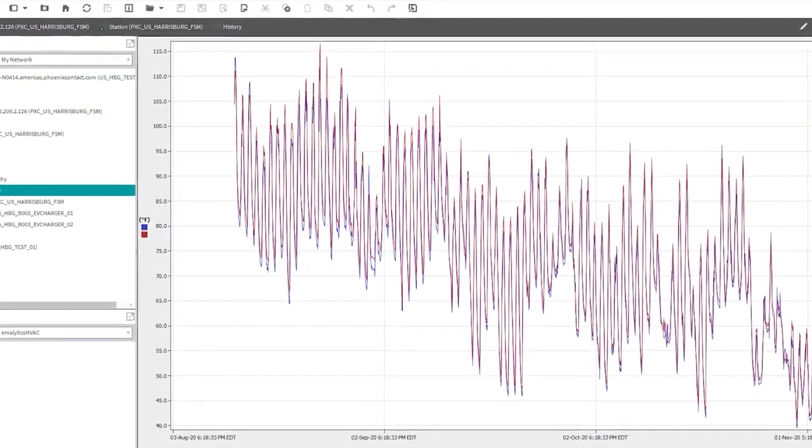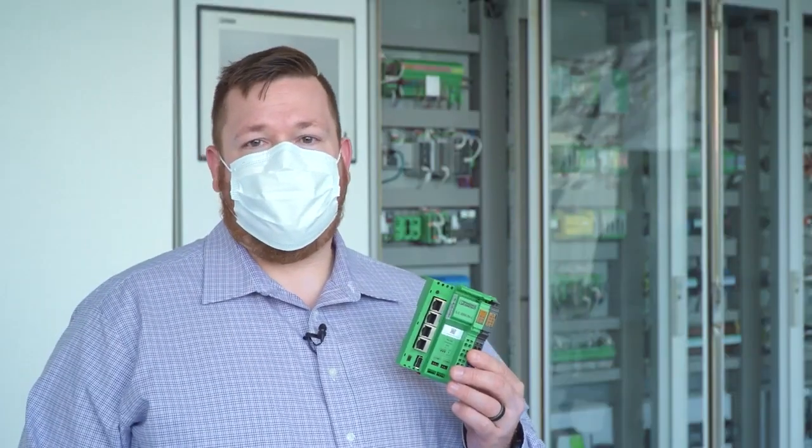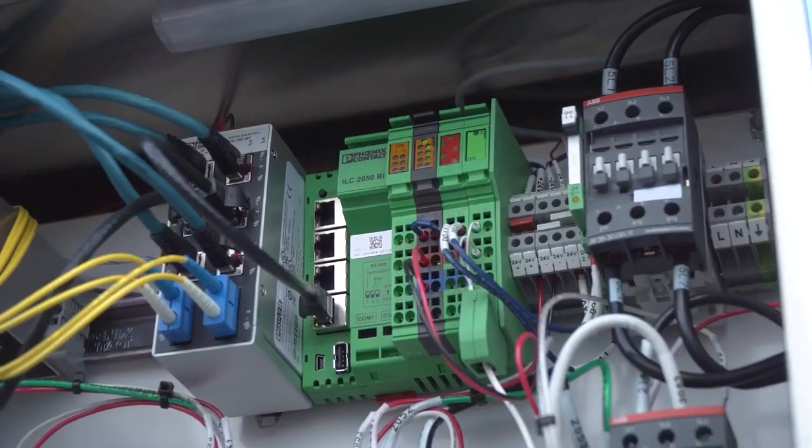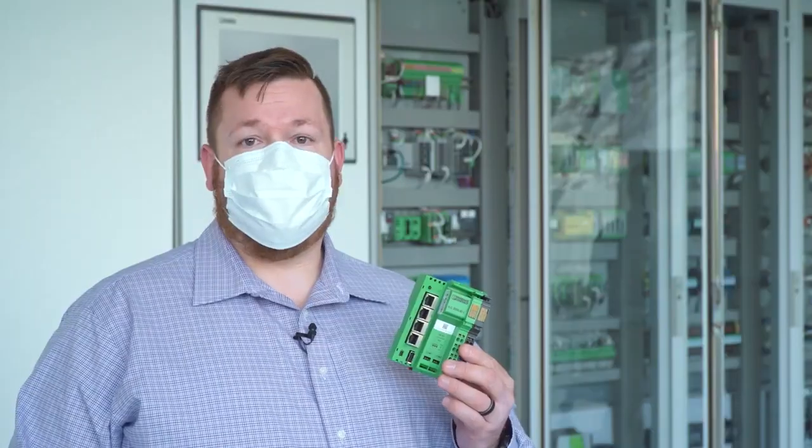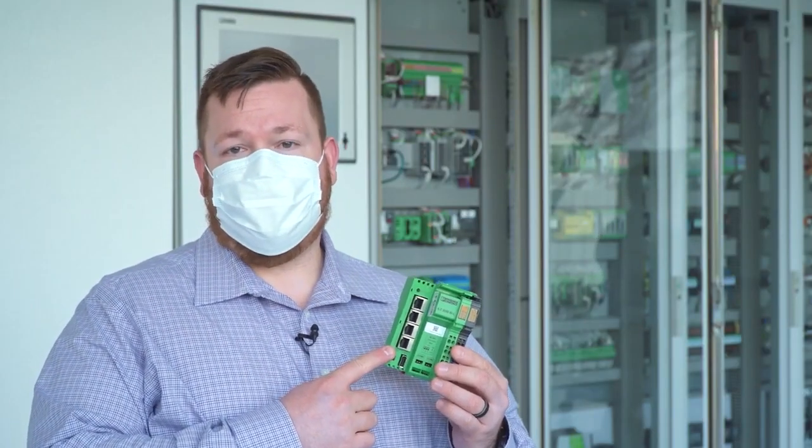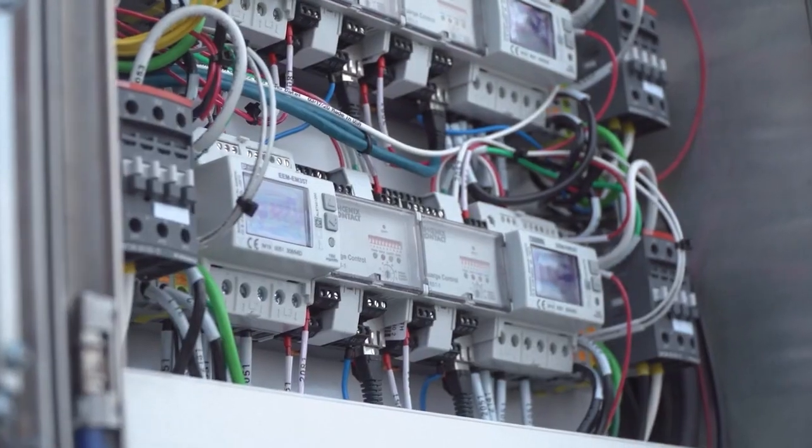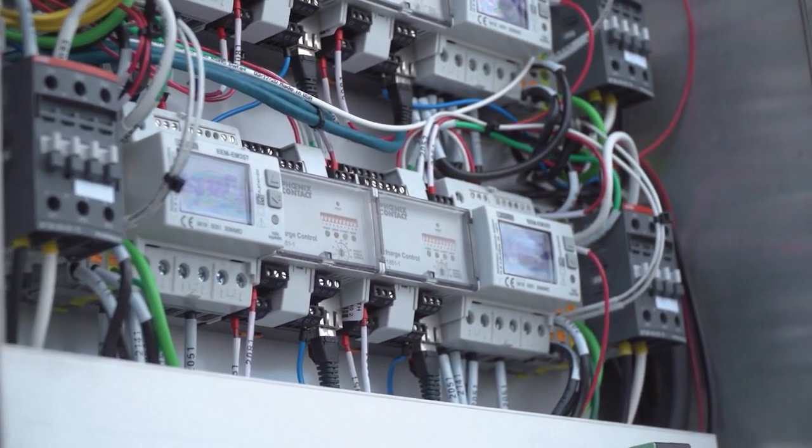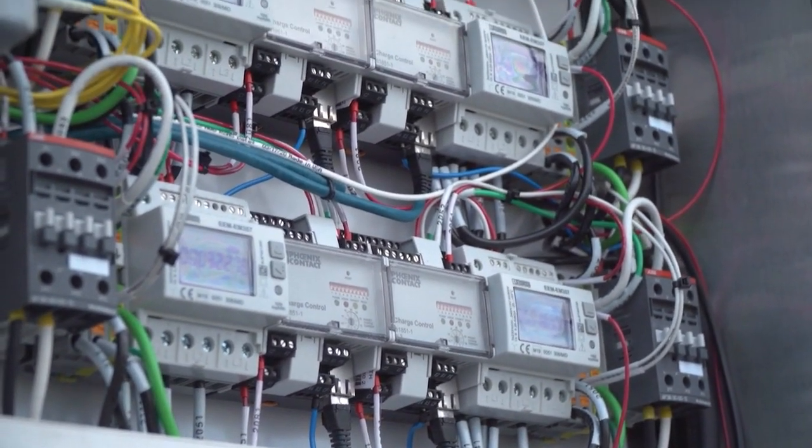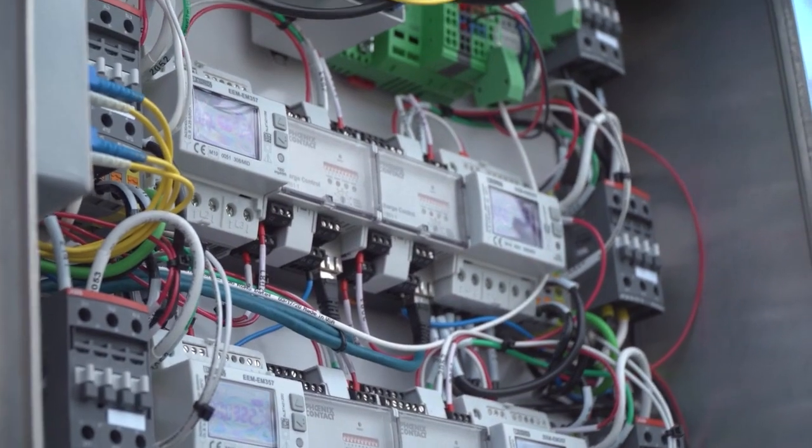When we upgraded the EV charging stations, the first thing we did was to replace the controllers with the new ILC 2050 running the Niagara framework. Secondly, we reworked the cabinet to add four additional power meters, the EM357, in order to monitor each power cable itself.